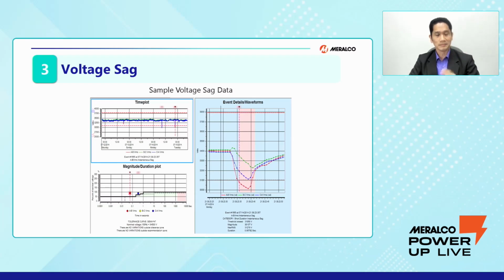So that is a voltage sag, and it might affect our operations, especially our motors and their contactors. But subjecting this voltage sag's magnitude and duration to the accepted industry standards for voltage sag, from the lower left, that is the SEMI F47 standard, or we could also use the ITIC curve standard, we could see that the voltage sag was within the safe envelope of the allowable SEMI F47 standard. It means that our equipment should be able to ride through this voltage sag and should not affect our operations or the equipment itself.